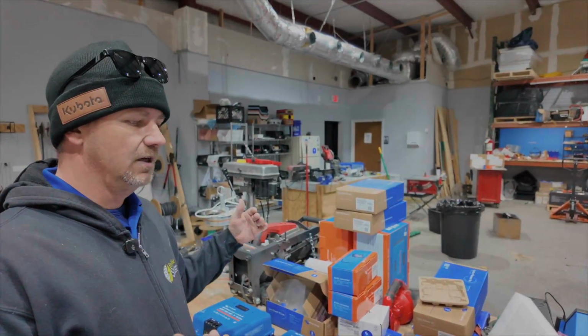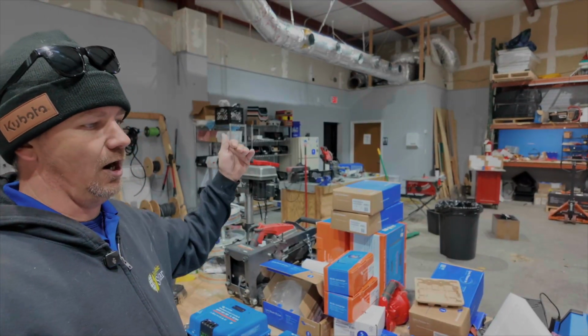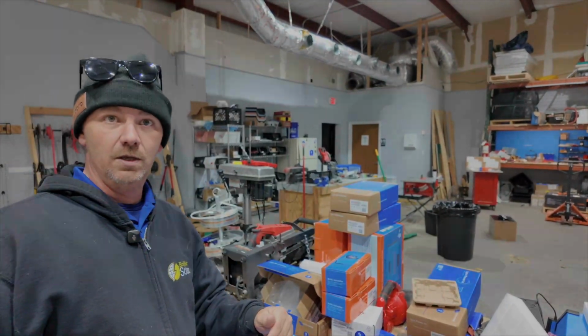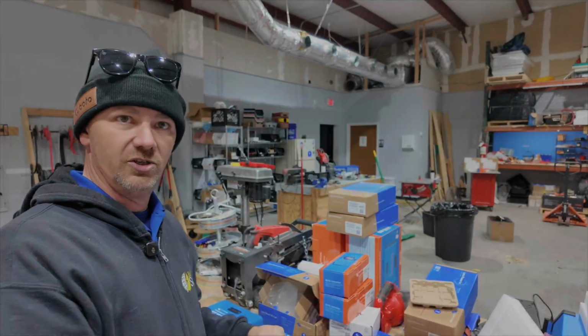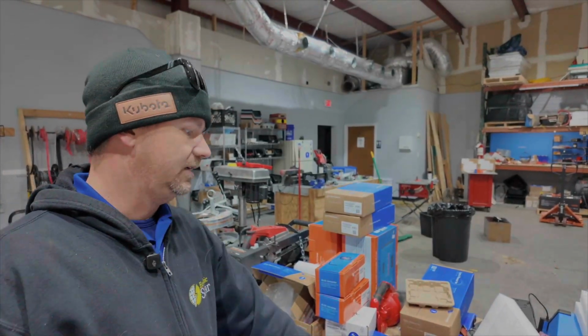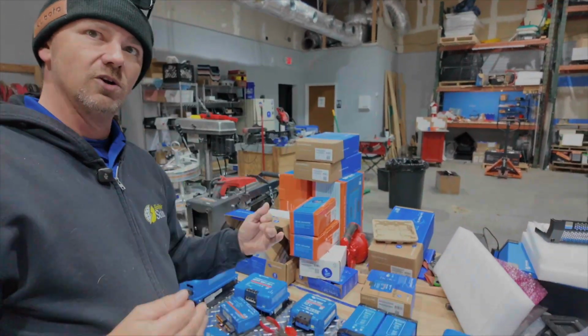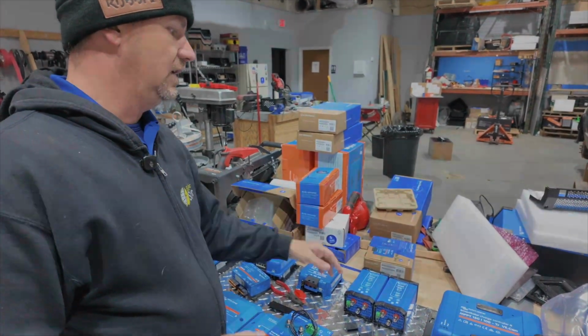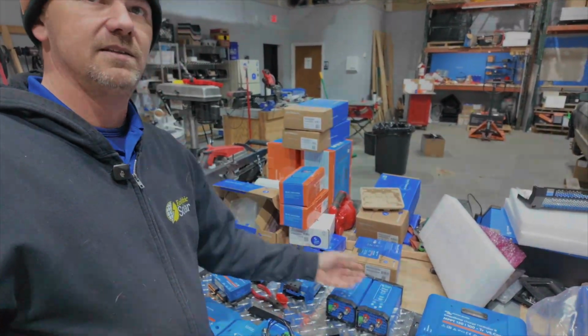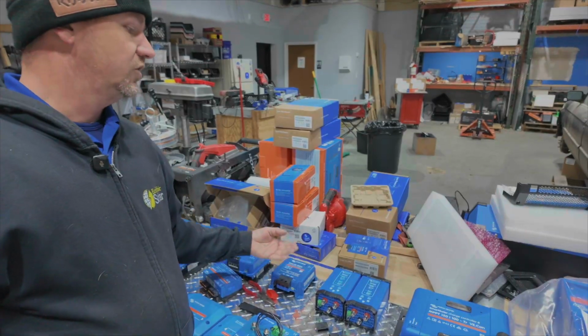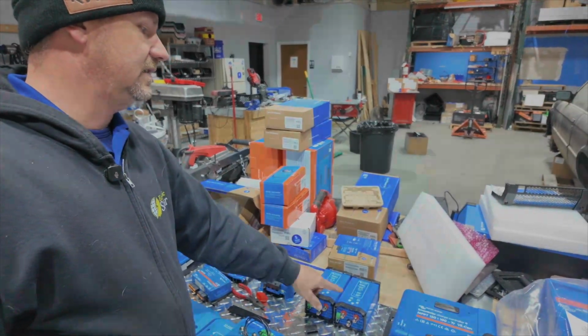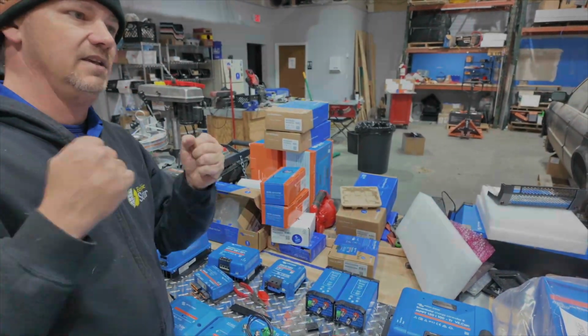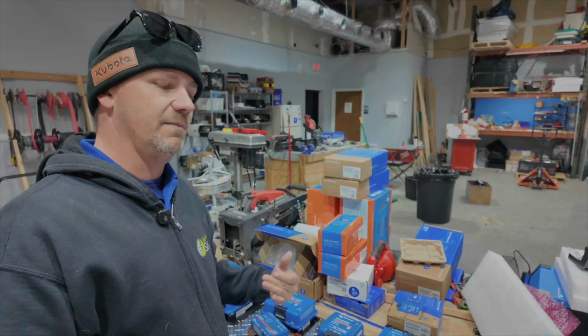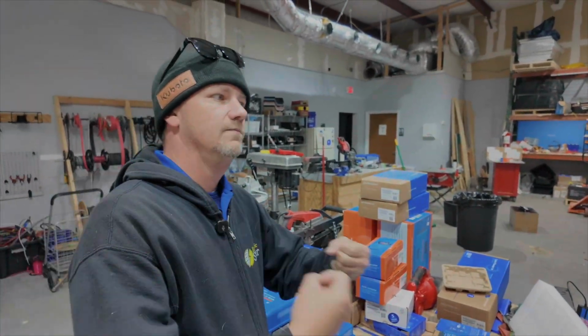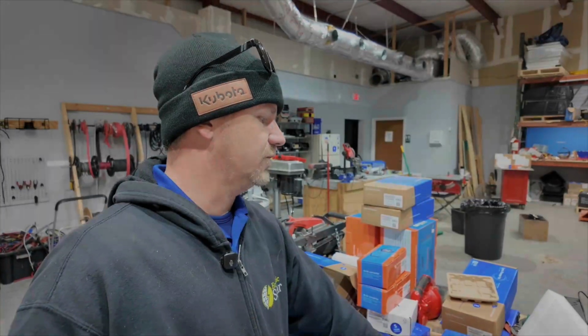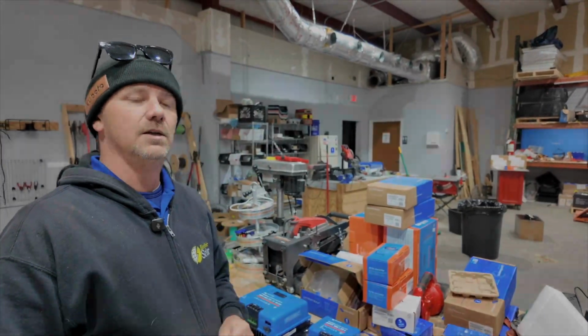So let's say we've hit a perfect storm and our state of charge is very low because now we need to start the generator. If we didn't have the buffer battery and the state of charge is low, these converters are directly related to how much is coming in, so the output can only give you so many amps, especially at a low state of charge. They can't dump the amount of current you'd need. That's where the buffer battery really shines.